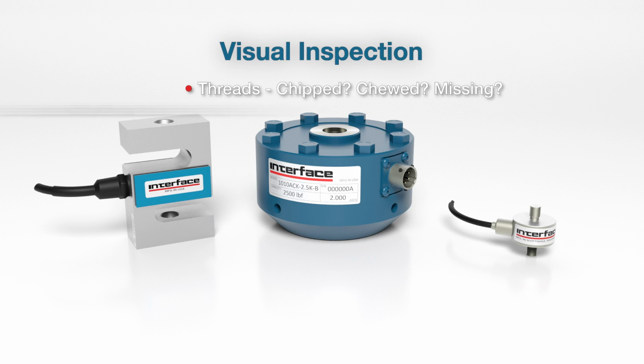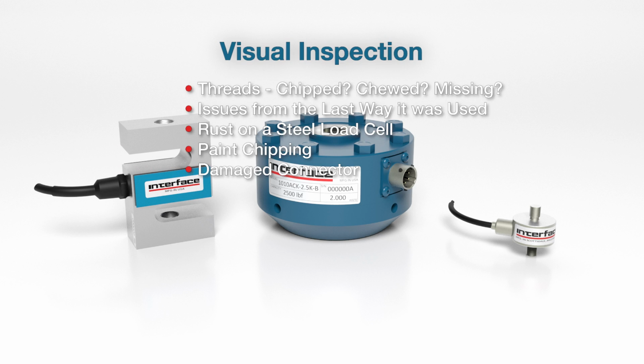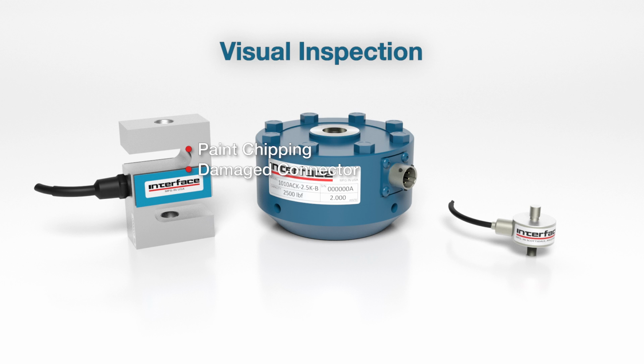So, all right, well, the first step should be pretty straightforward, and that's going to be a physical inspection. You want to make sure the sensor looks like it's in good working condition. Some visual clues would be the thread details, any signs of rust if it's been left out in the elements for too long, where it shouldn't have been. Or if it's just physically damaged in any way, it could include the connector as well. So make sure the pins all look healthy in that regard as well. If you've got a new unit, then that's pretty straightforward, and we can move on to the next step there.